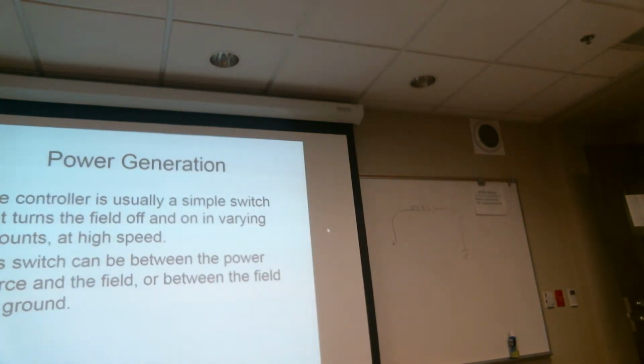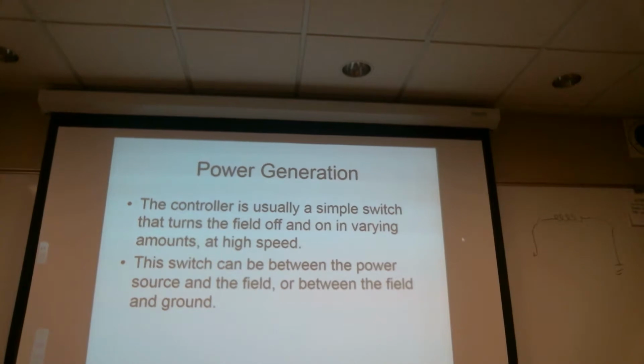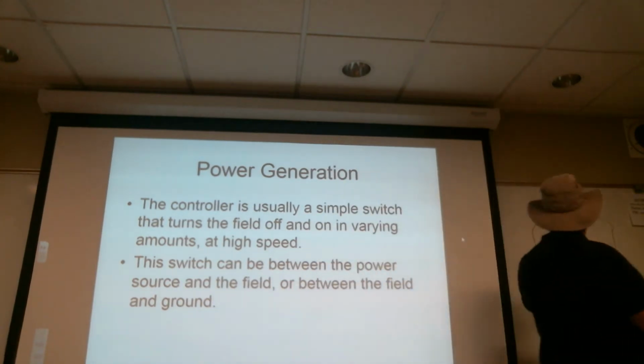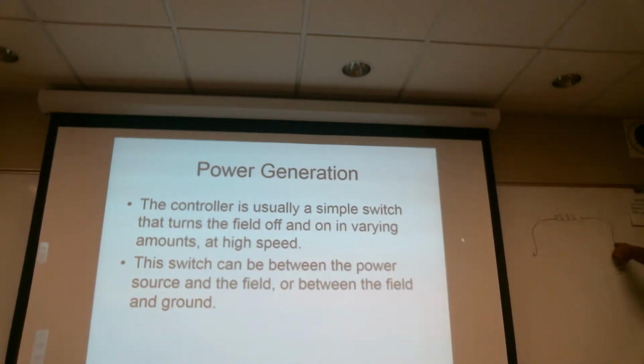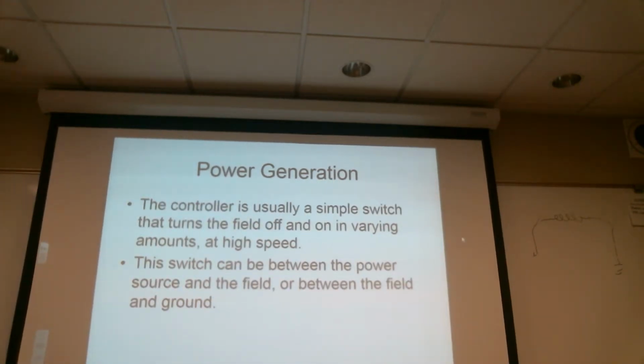And that matters particularly when we get into carbon pile regulators, because with a carbon pile regulator, part of how you hook it up has to maintain the correct polarity. The part that goes to the field doesn't, but the part that senses voltage does have to maintain polarity. So I can't take my carbon pile regulator and just flip it around into here. It's got to maintain the exact same orientation, or it'll read backwards. As the voltage goes up, it'll try to cause the voltage to go even higher.